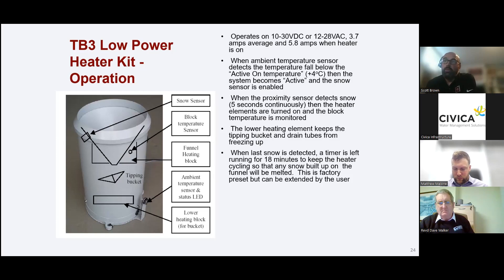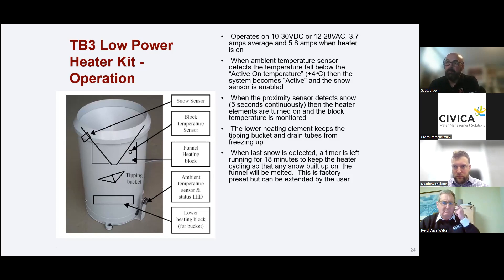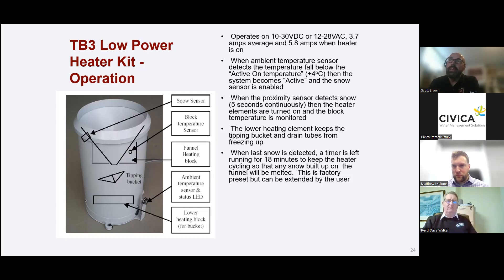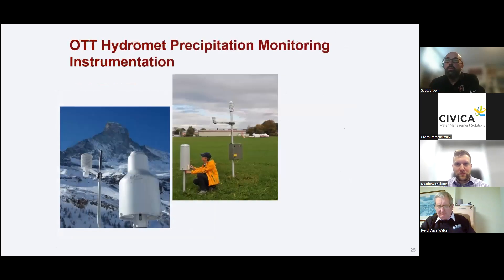The heated tipping bucket is meant to give a rough estimation of snowfall — it is not an absolute gauge for snow. There are some timing issues with the low-power heater kit, and if snow is a major concern, you need to look at other options for gauging instrumentation.